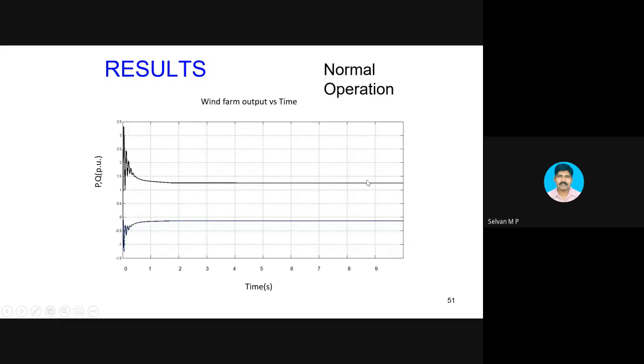That is the rated power output. I'm sorry, it's slightly less than 1.5 megawatt. This is 1 per unit and this is 1.5. The graph is here, so less than 1.5 megawatt. The total rating is 1.5 megawatt. That is at rated wind velocity. If the wind velocity is less, the output is going to be less. So during that time, it draws very less quantity of reactive power, so no problem at all. The capacitor that is available is able to supply that reactive power.